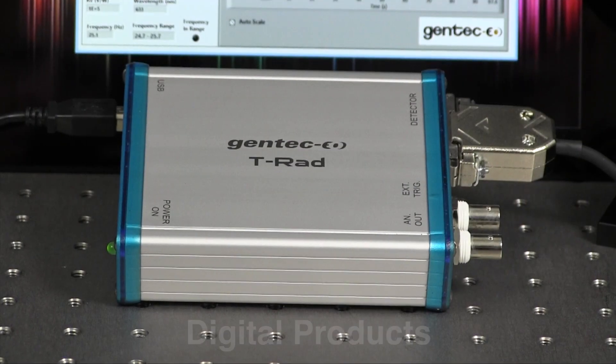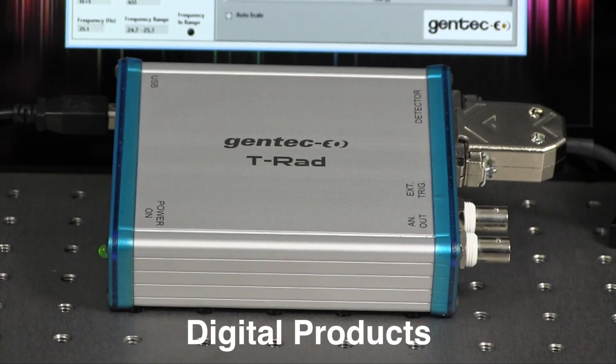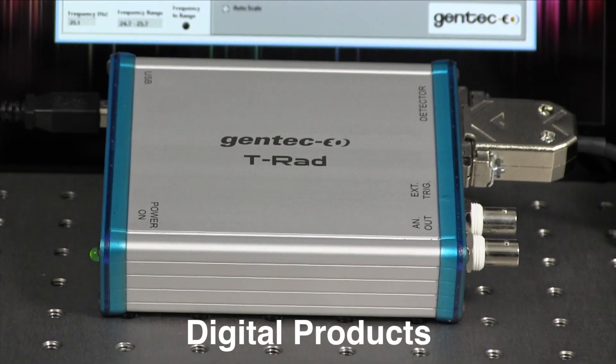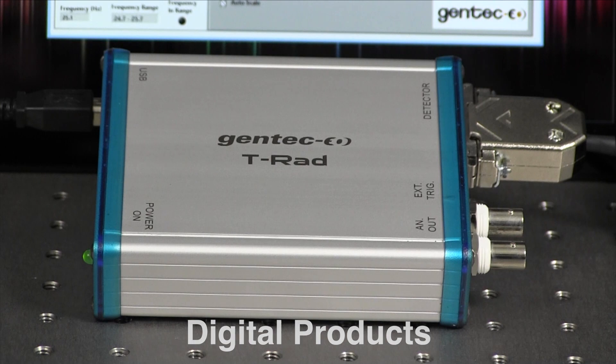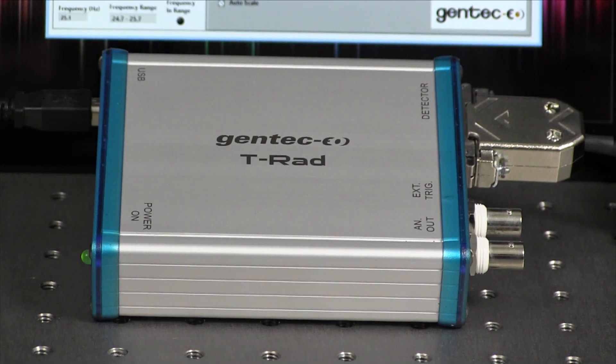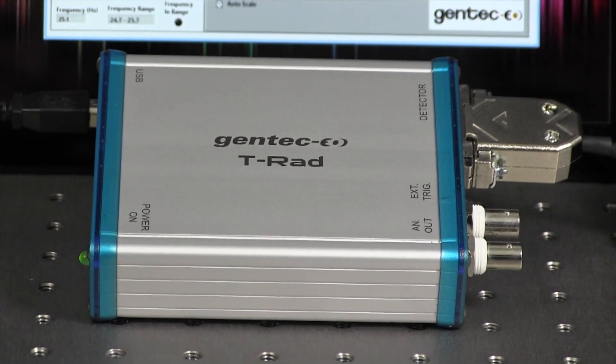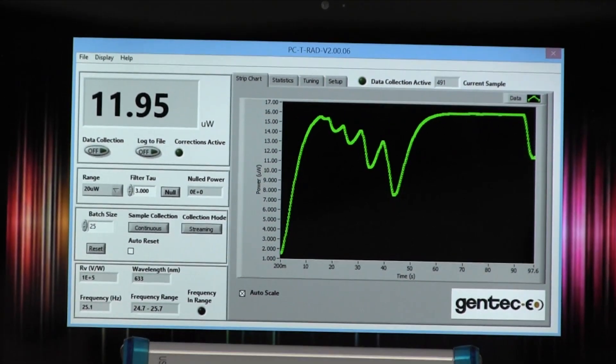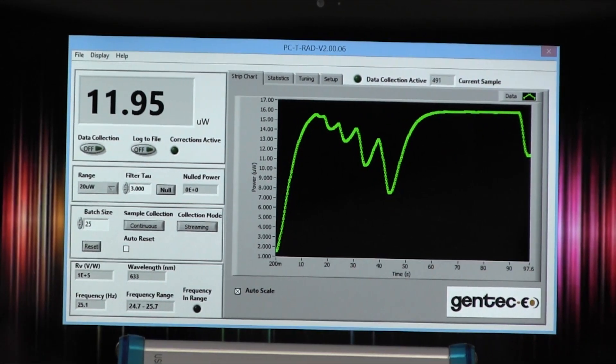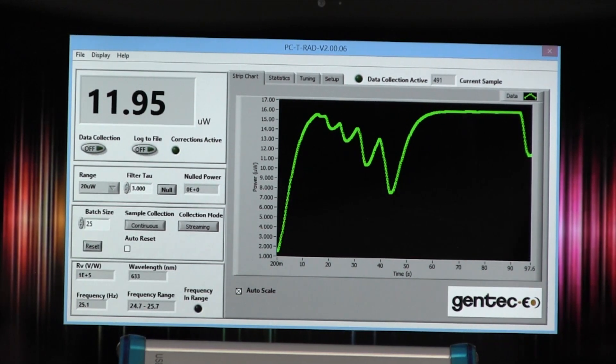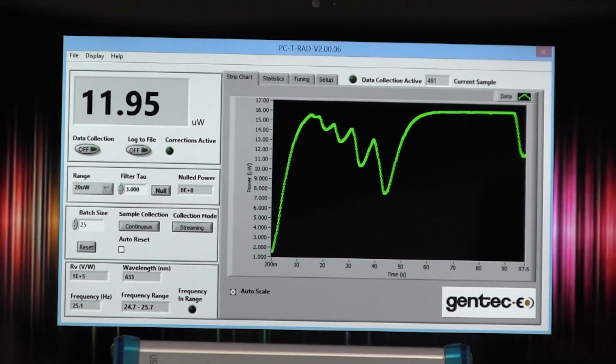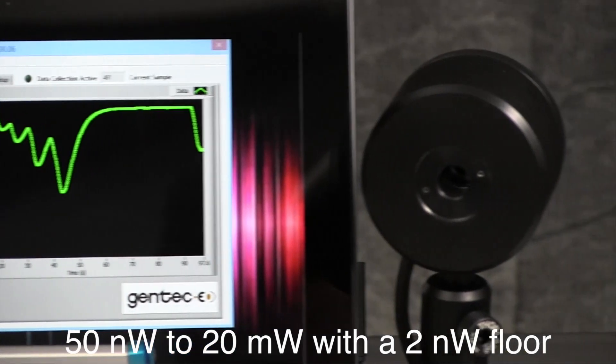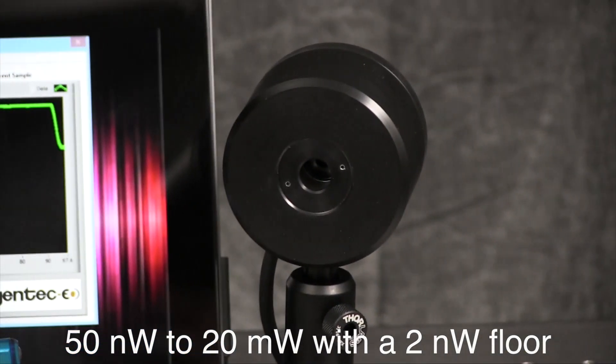In 2015, we redesigned our terahertz DSP lock-in radiometer to make it easier to integrate into your digital terahertz measurement system and to allow firmware upgrades in the field. The T-RAD with standalone LabVIEW software and our terahertz pyroelectric detectors provide power measurement of far IR and terahertz sources from 50 nanowatts to 20 milliwatts with a 2 nanowatt noise floor.